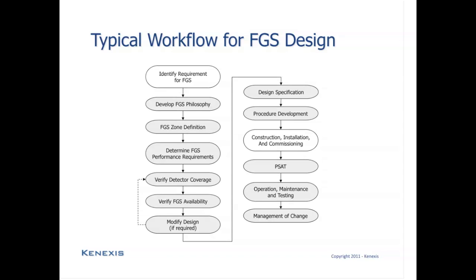We will first verify the coverage using quantitative models to calculate the coverage that has been actually achieved in a zone and compare that against the target. And then we will use the traditional SIL verification techniques to calculate the fire and gas system availability. And these are the same techniques that are being used for IEC 61511, and the best source for the techniques and tools for fire and gas system availability calculation would be the ISA technical report on SIL verification, technical report TR 84.00.02.